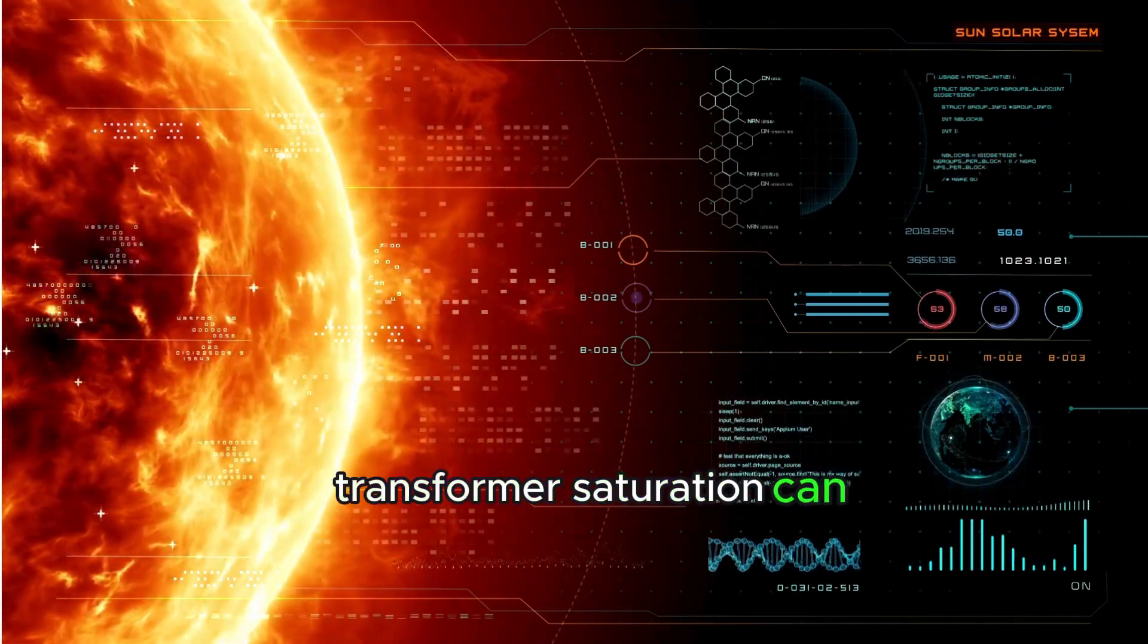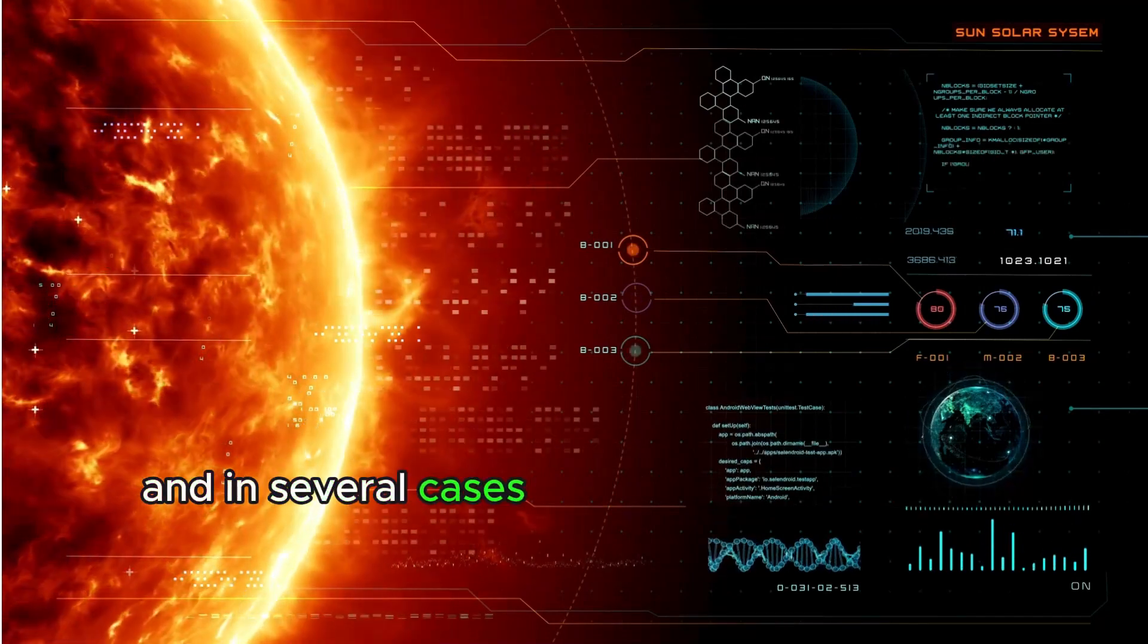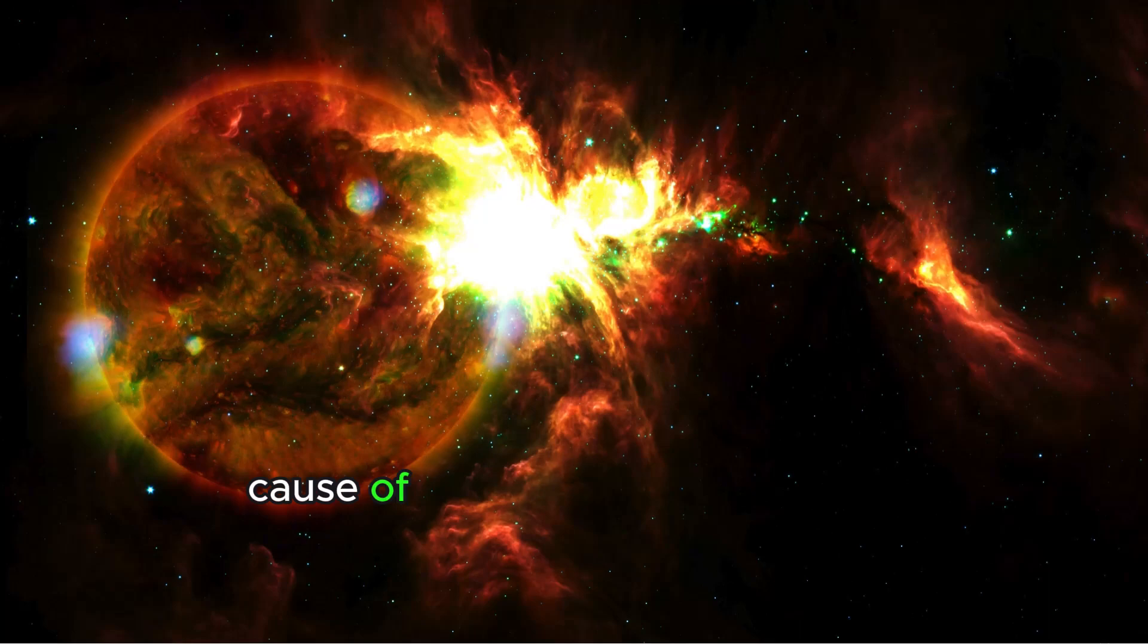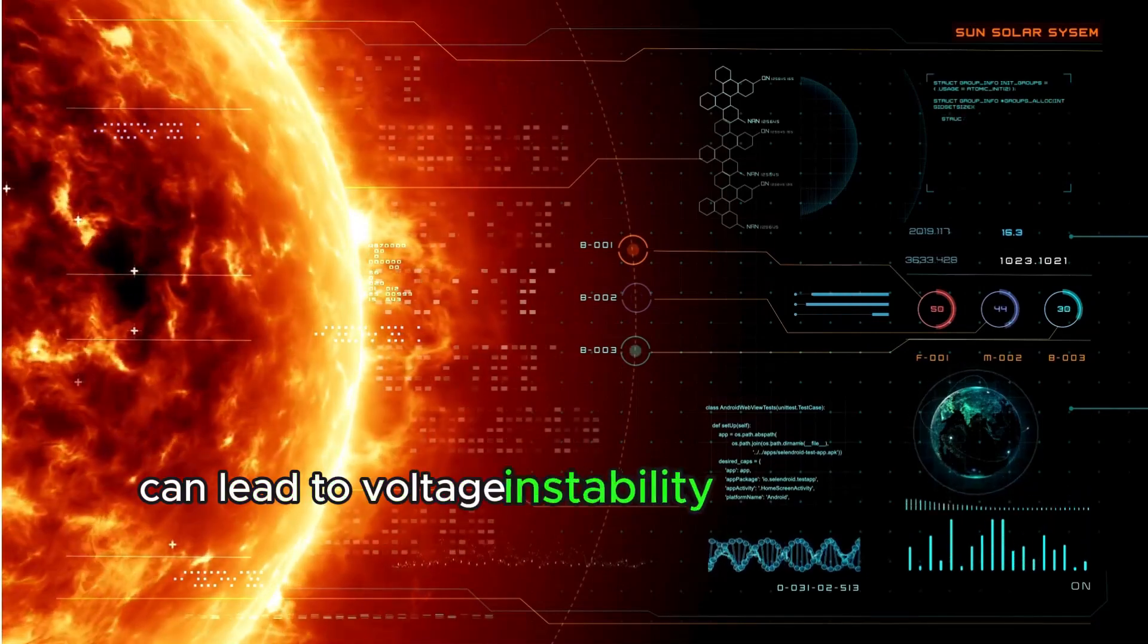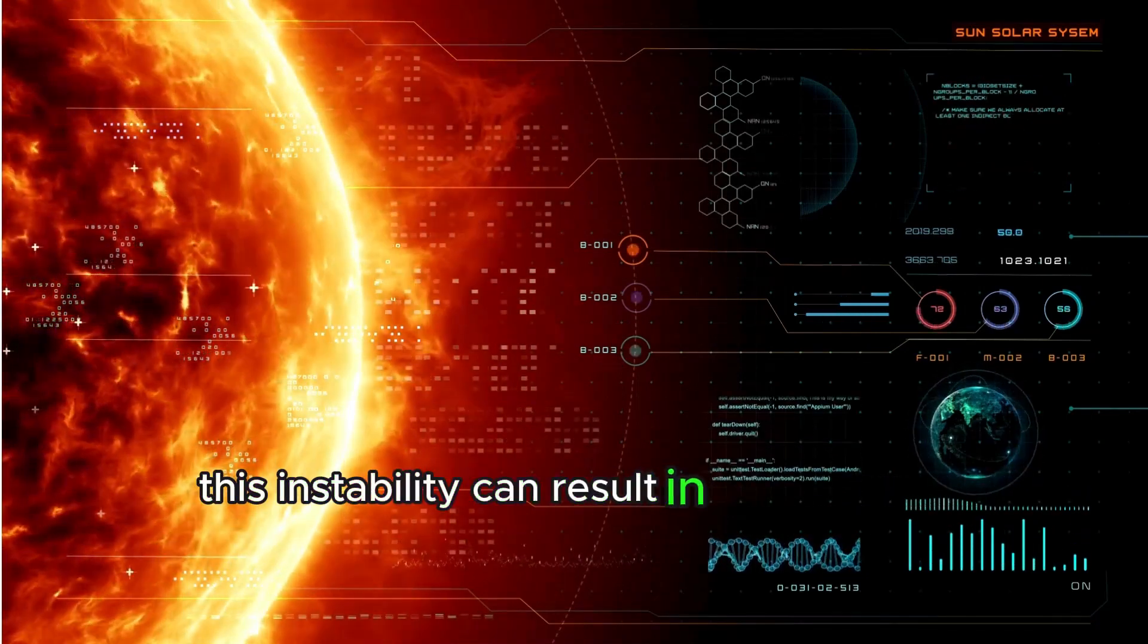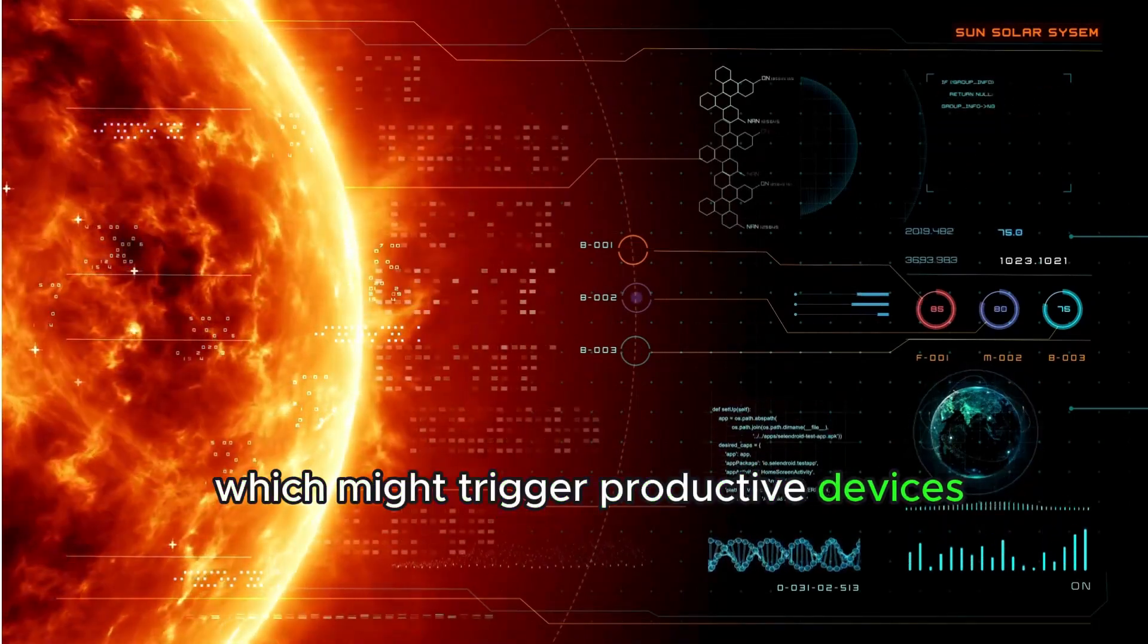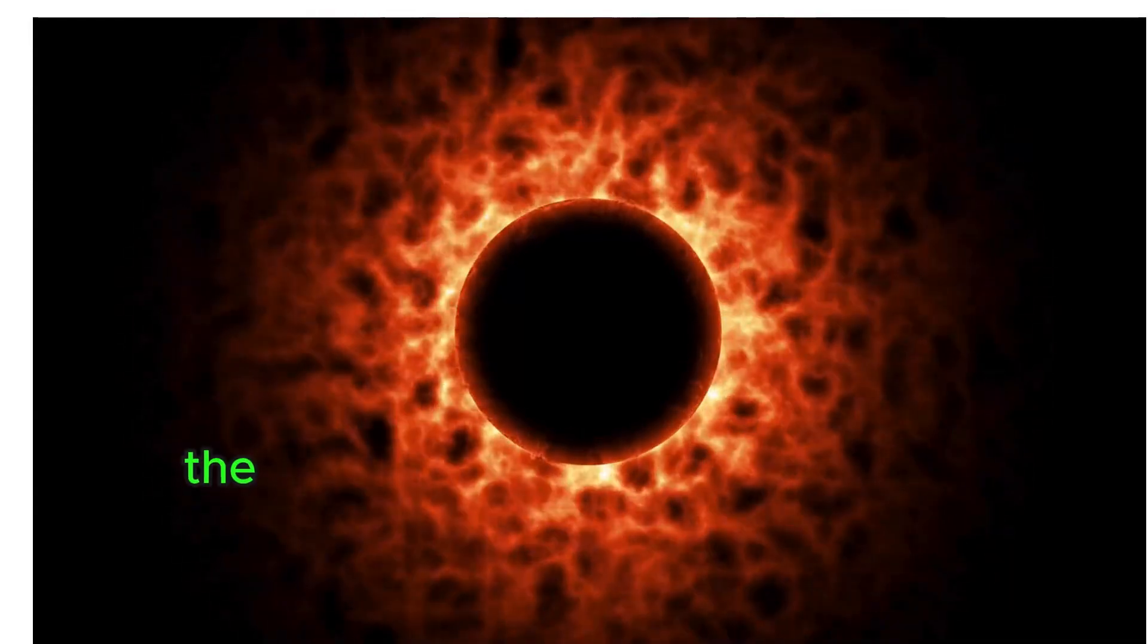Transformer saturation can reduce the efficiency of the power grid and in severe cases lead to transformer failure. The second phenomenon because of GICs is voltage instability. The presence of GICs can lead to voltage instability in the power grid. This instability can result in voltage drops which might trigger protective devices and lead to blackouts.